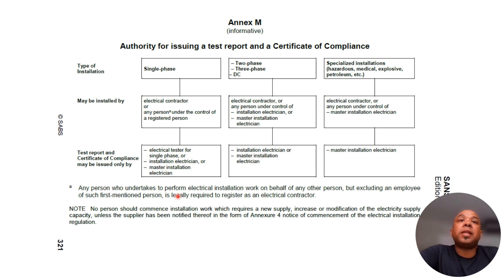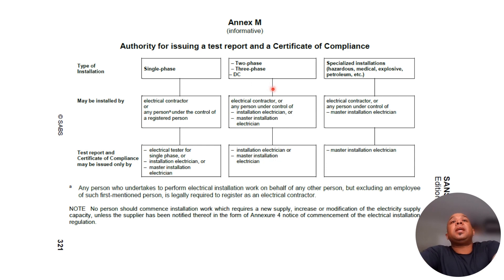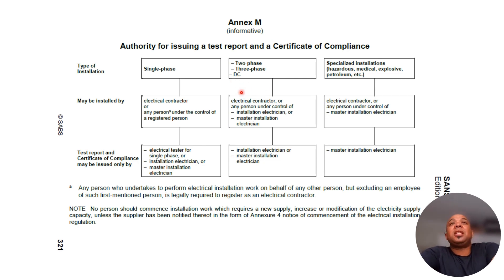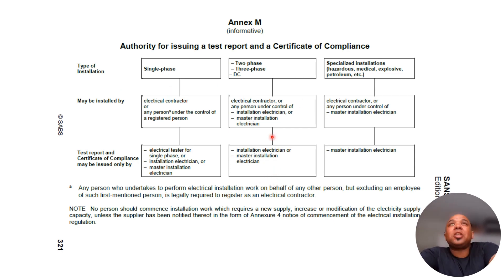Here's an interesting point: if you're a single phase tester and someone is connecting your inverter or solar system — which is DC — and they say they'll issue you a certificate of compliance, technically it's not valid. A single phase tester cannot issue a certificate of compliance for a DC solar or inverter installation.